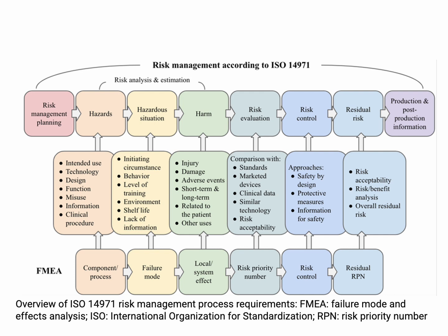Of course, when we are looking into the documentation for a medical device, we are going to produce documents related to whatever is applicable, but related to all of these different topics on the top. So the risk management planning, the hazardous situations. Now you can have one document going over these requirements for ISO 14971. But this is in a nutshell how the risk is managed.